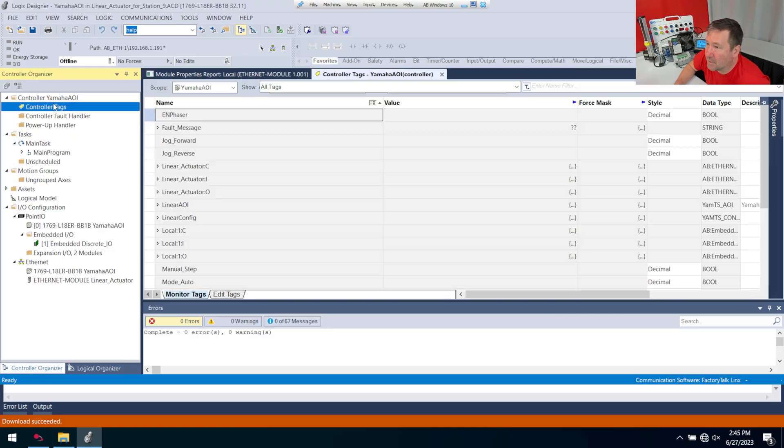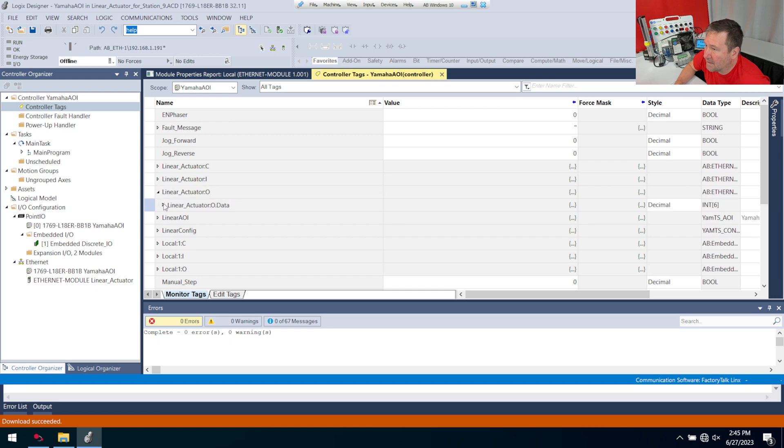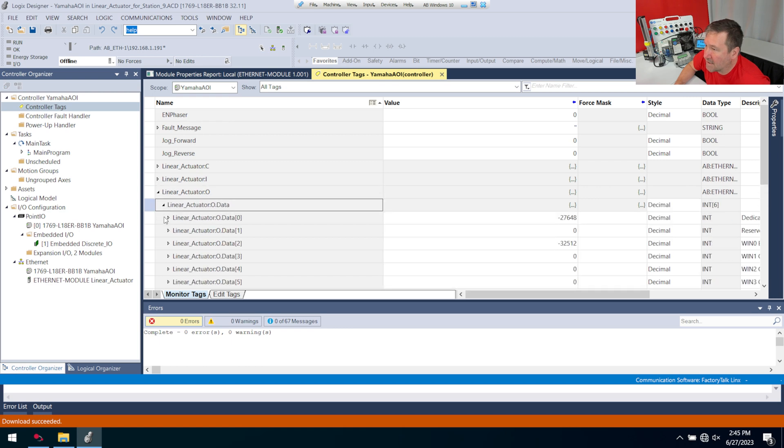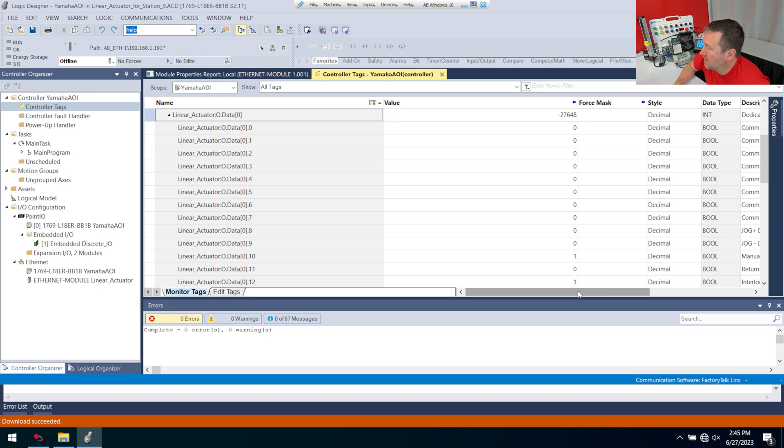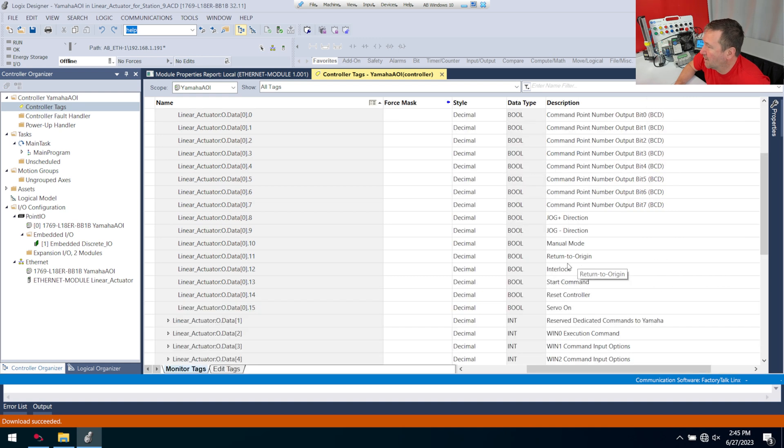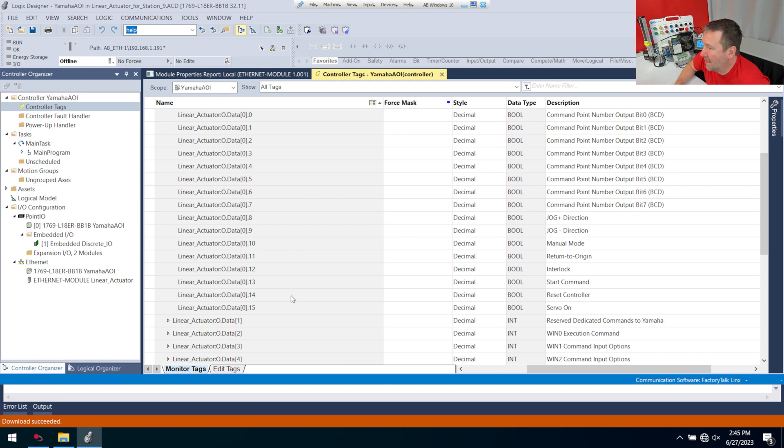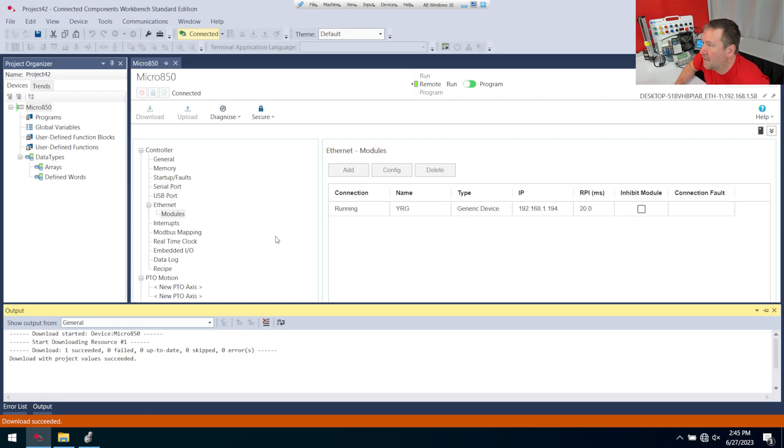I'm going to open up my controller tags in Studio 5000 and go to the outputs, because they bring in the descriptions, and then it'll let me know what I need to do here. I'm going to need to turn my interlock on, which is 12. I'm going to need to put it in manual mode, which is 10, and 15 is going to be servo on.